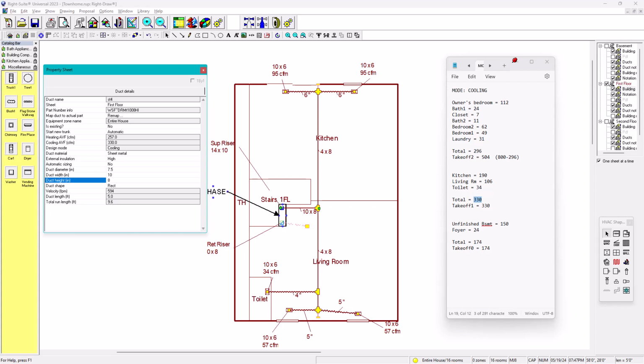Because generally, you want to keep the height smaller because there are a lot of issues with the architect. The architect will tell you the flatter your ducts, the better. Because imagine if you have a high duct, then you will need more ceiling space. They don't want shorter ceilings, right? So in this case, we're going to have 10 by 8, and then it says 594 FPM.